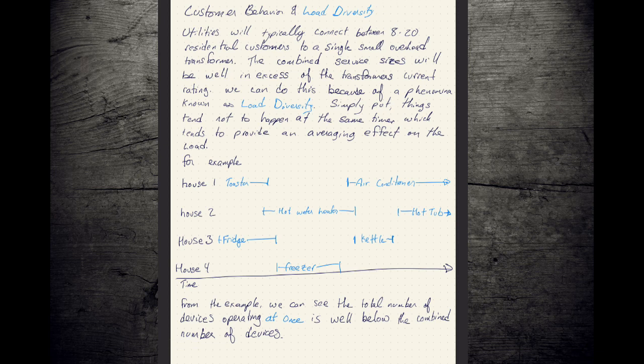Second thing we've got to look out for is a thing known as load diversity. So when a utility is connecting its customers, you might have a 200 amp service in your house. If your house is older, it might be a 100 amp service. That doesn't mean that your house is always flowing 100 or 200 amps. Most 200 amp services never come anywhere near flowing 200 amps continuously. And so as a utility, it would be incredibly wasteful and very expensive if we were to say, okay, we've got 4 houses, 200 amps each, I need transformation that can handle 800 amps. That's not how it works when we're sizing our equipment. That would be incredibly expensive and honestly very wasteful, because we know that it's likely those houses would never hit their 200 amps that the service would support. And even if they did, it'd be incredibly unlikely that they'd all hit it at the same time.